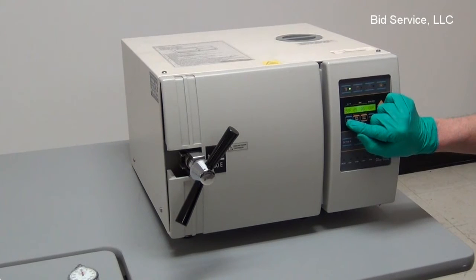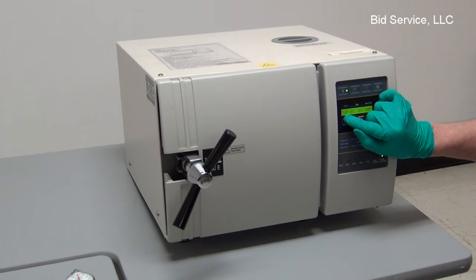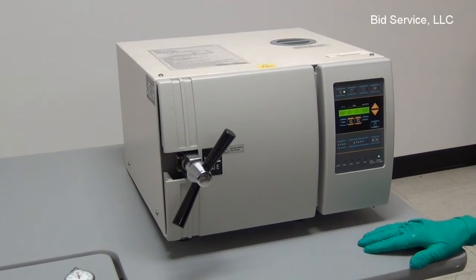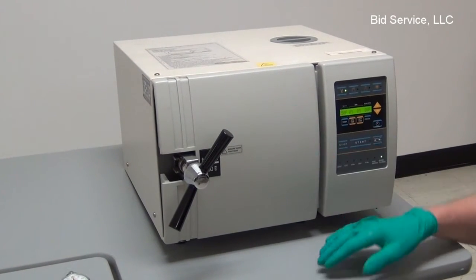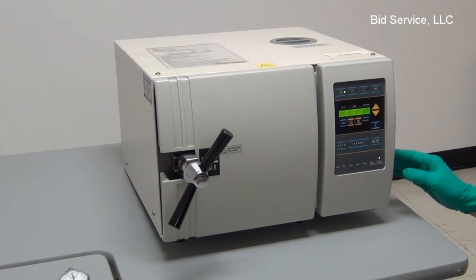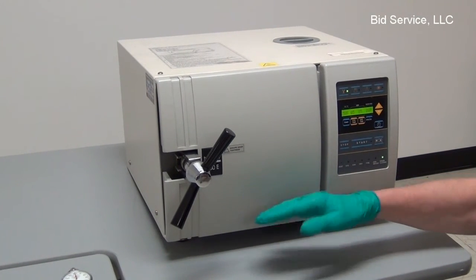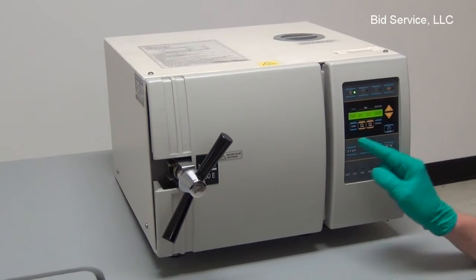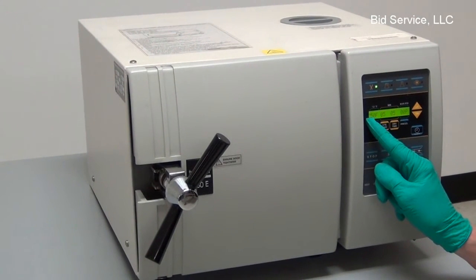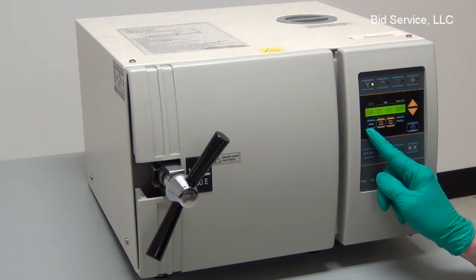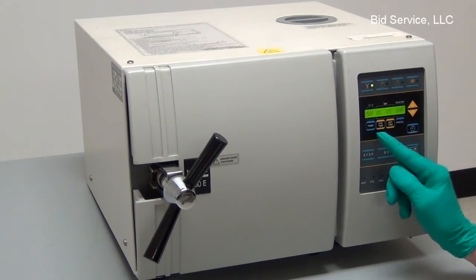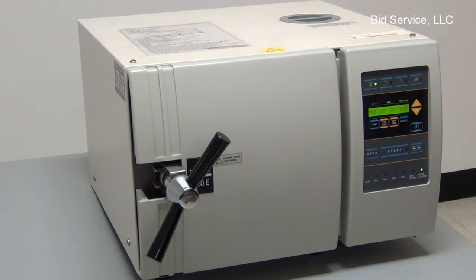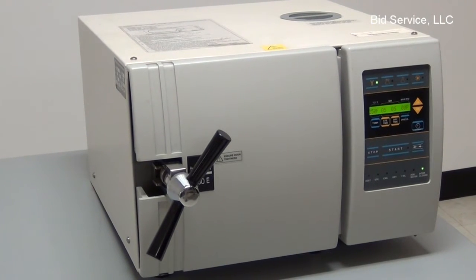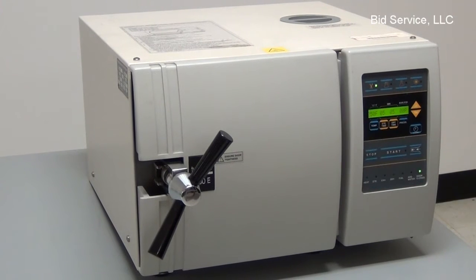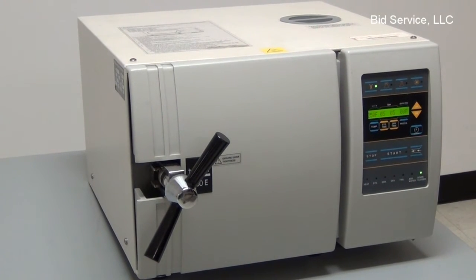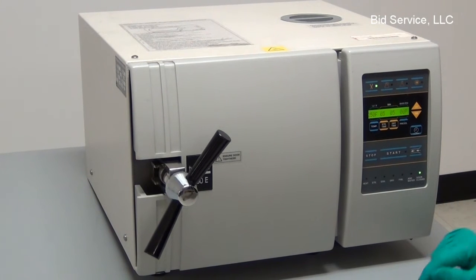We set up the temperature for 250 degrees Fahrenheit. That means the autoclave will start to heat up. The normal process is it will fill partially with water. The heating process will begin, and once the temperature reaches its set point of 250 degrees, it will then switch to sterilization time. Typically these times can be 30 minutes, 60 minutes, depending on the type of material or instrument that's being sterilized. For purposes of our demonstration, I've set it to 5 minutes.